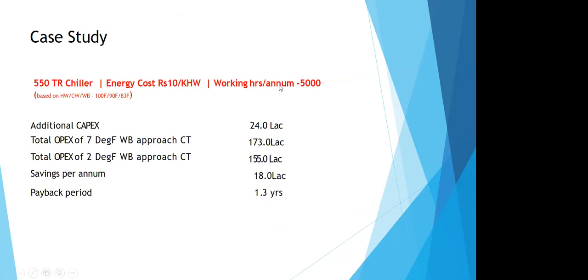Now we look at a real case study for the low approach tower. Here we have taken the same capacity of 550 tons, an energy cost of around 10 rupees per kilowatt hour, and assuming that the chiller is working for 5,000 running hours per annum. These are the standard conditions for North India. We have considered 83 Fahrenheit as the wet bulb, an approach of 7 degrees and a range of 10 degrees. The additional cost paid for the low approach cooling tower, the capex, is around 24 lakhs for a 550 TR chiller.